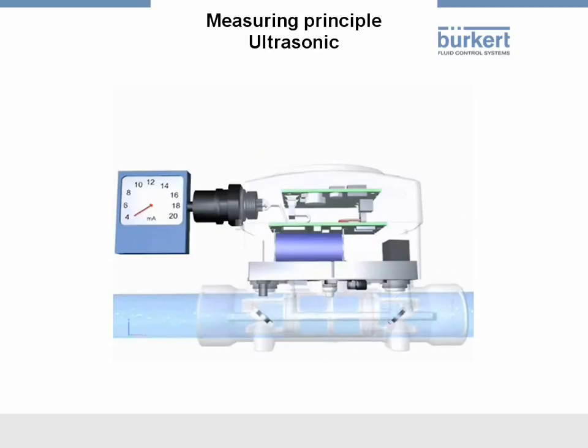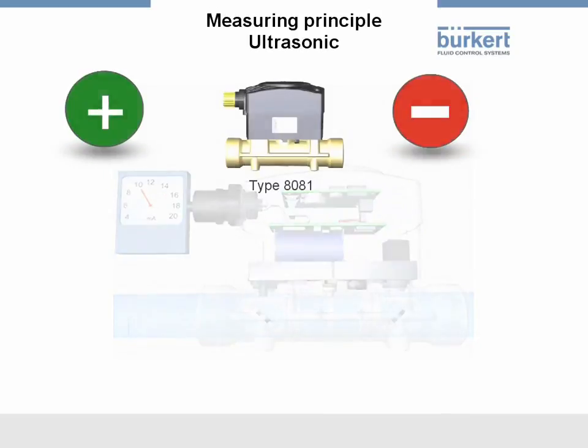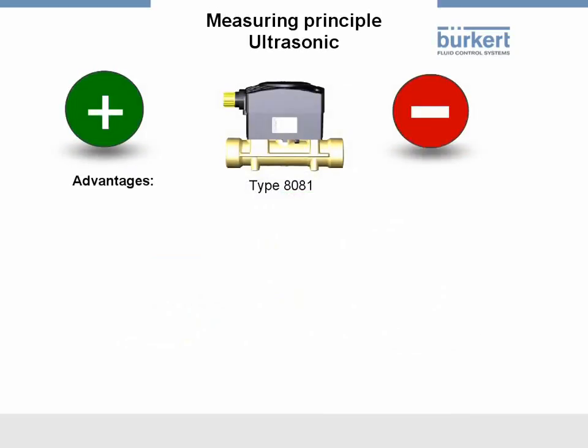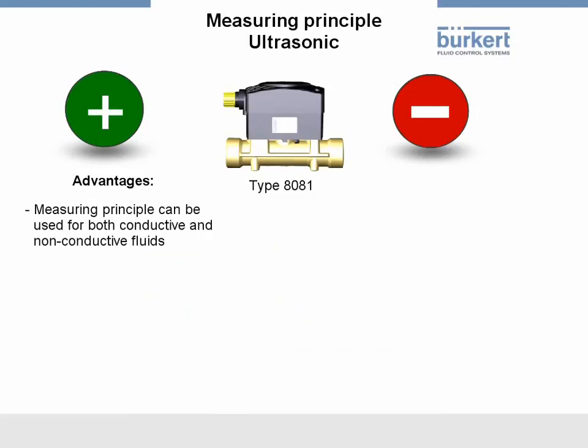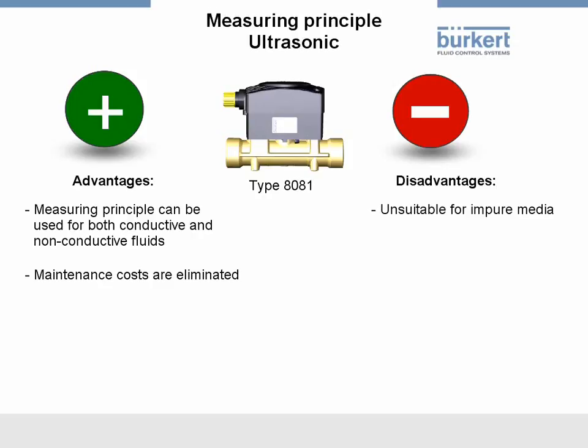The propagation time required by the sound wave in the direction of flow is shorter than the time against the direction of flow. The difference in the propagation times is directly proportional to the flow rate. This measuring principle can be used for both conductive and non-conductive fluids. Since there are no moving parts installed inside the unit, the disadvantages and higher maintenance costs associated with moving parts are eliminated. The disadvantage of this measuring method is that it's unsuitable for impure media and media containing air.